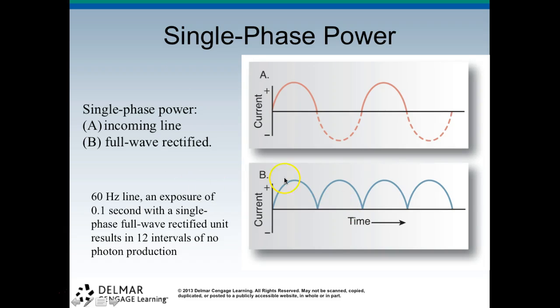So here's single phase, so the incoming power you can see here, and it drops to zero, and then we have it here and it drops to zero. That's why we have that 70.7%. And then here, this 60 hertz line, an exposure of 0.1 second with the single phase full rectified unit. So that's where you see those diodes where we're rectifying it. So here you can see we dropped to zero, but there is no lag here. So we dropped to zero with each cycle, but no lag. So we call this pulsed here. So this is 6 pulse and there's 12 pulse.